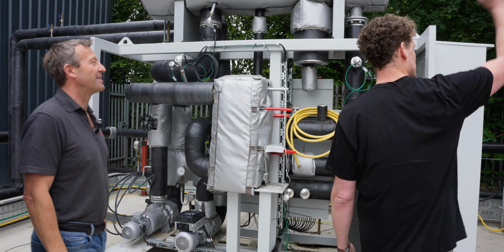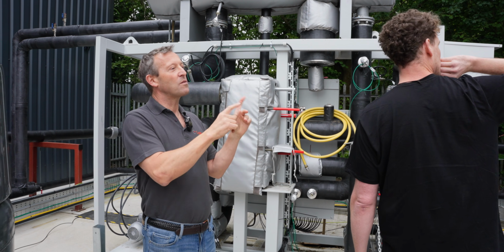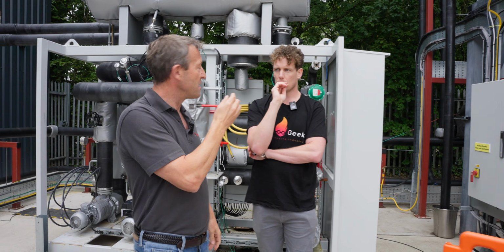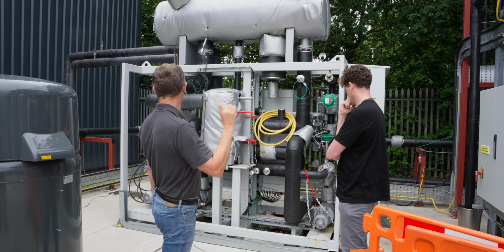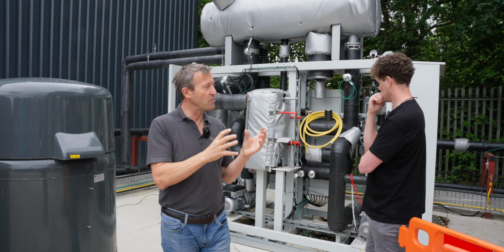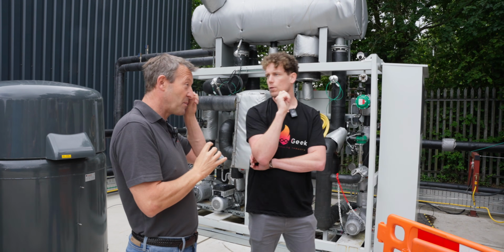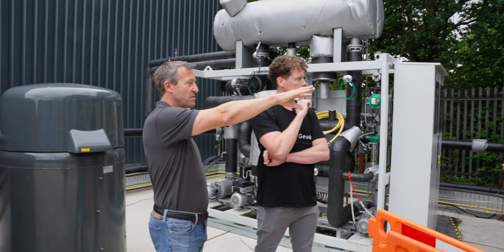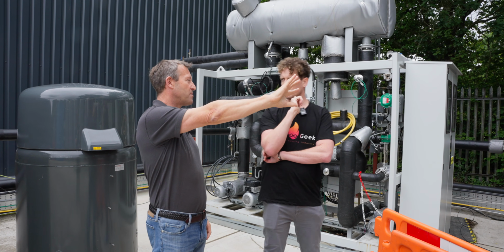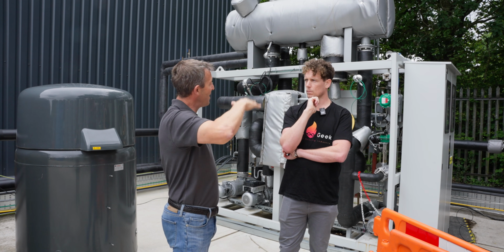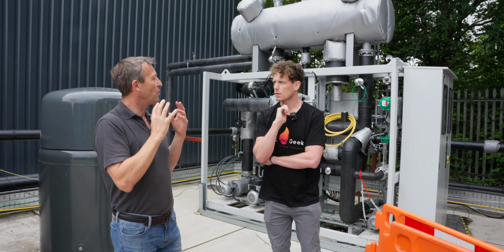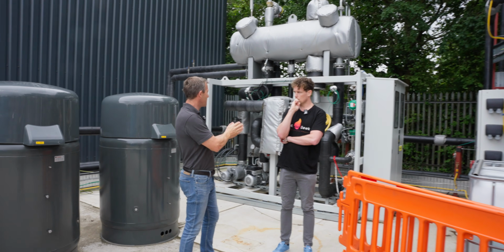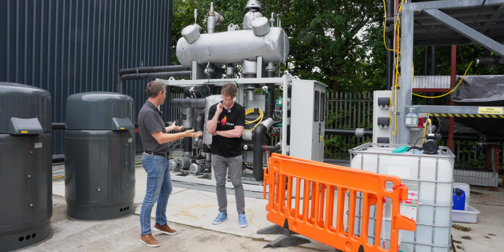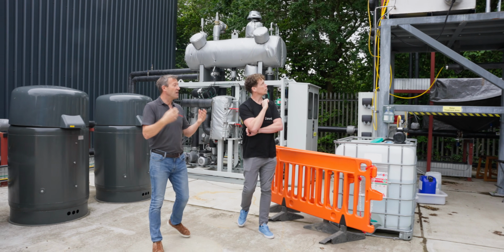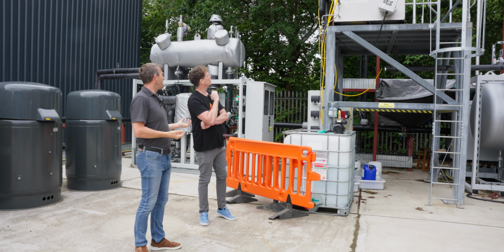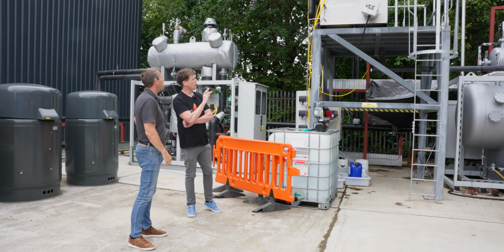That's the water that goes into the shell and tube heat exchanger. Yes, the water in our circuit - there's only a little tank in our circuit, just around that side. We only have a relatively small amount of water, which makes it really safe. Most of the water is on the customer side. With a traditional gas boiler, you have to make sure it never drops below a certain level or the tubes get too hot, whereas we have hardly any water in our system - it's almost completely dry. All the energy is stored in the aluminium and rock, so it's much better for unmanned operation and fundamentally safer because we can't overheat the system.